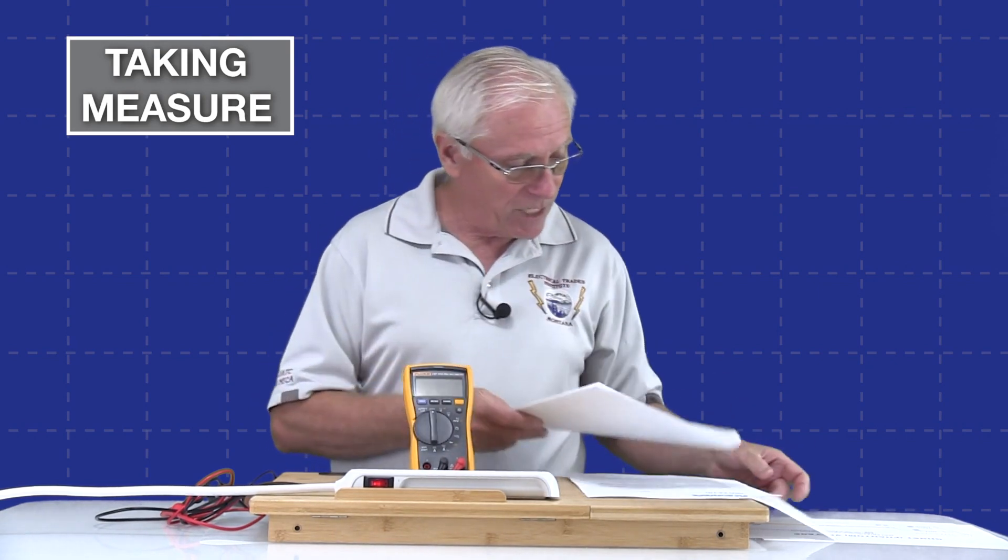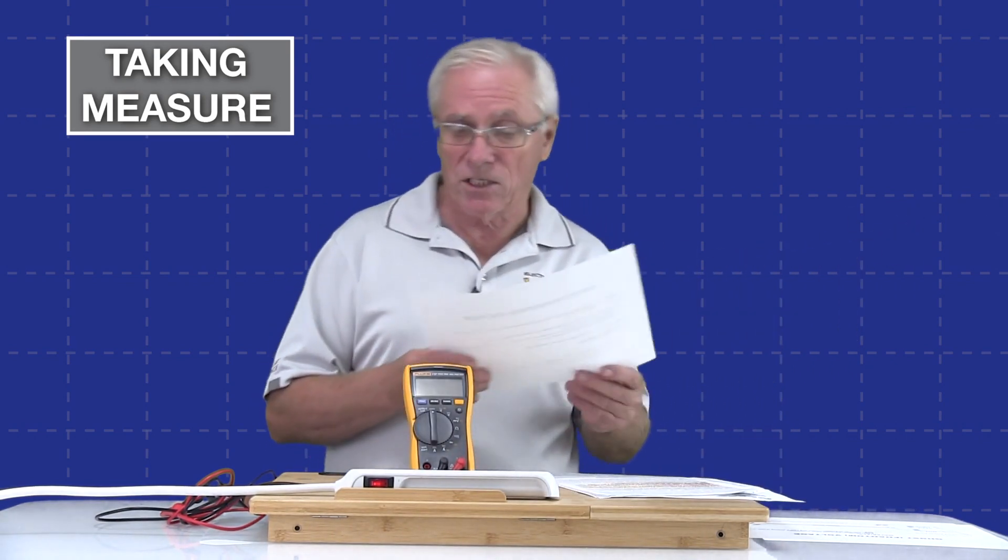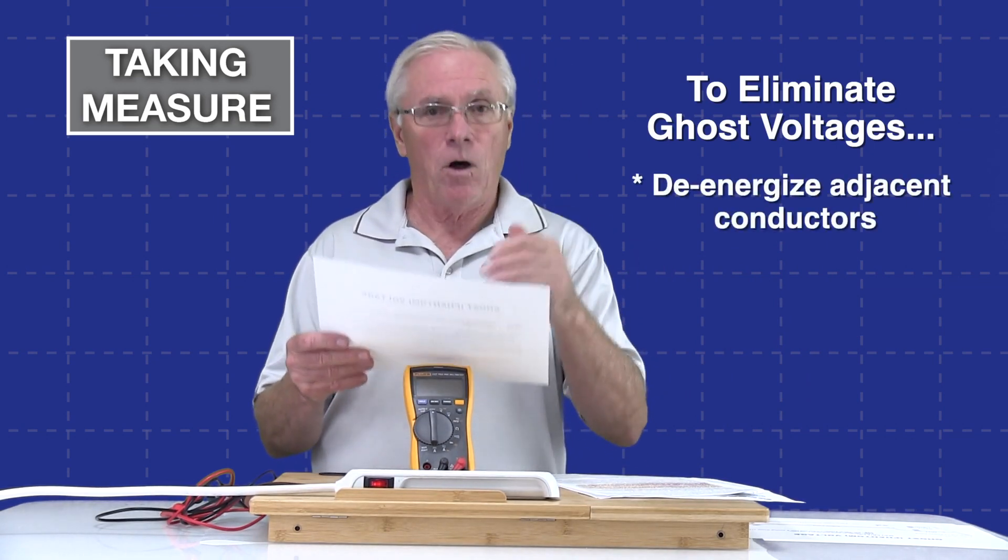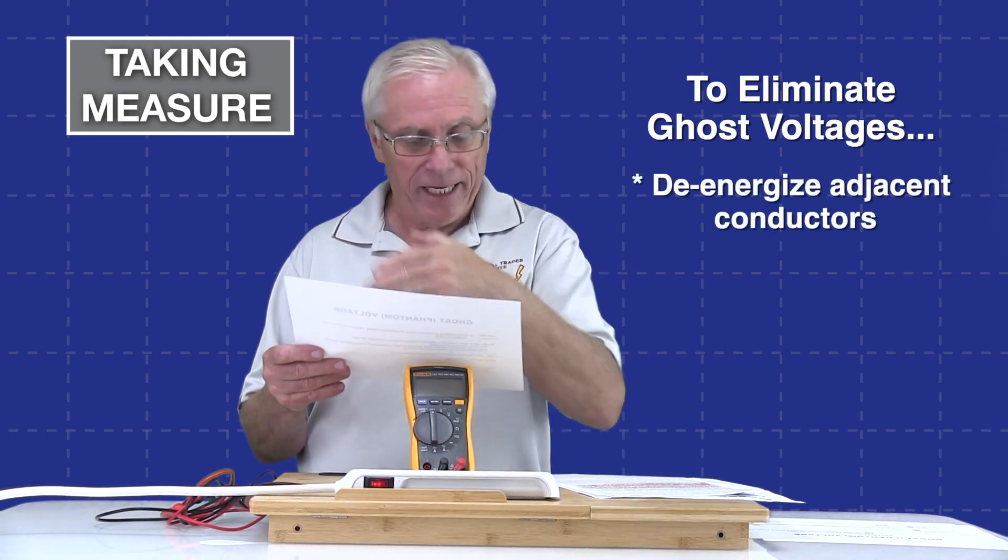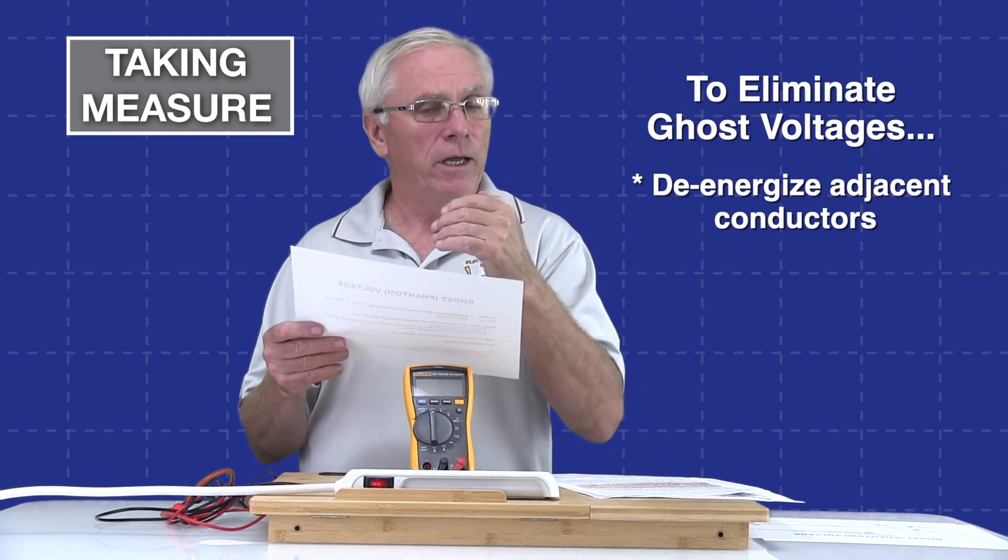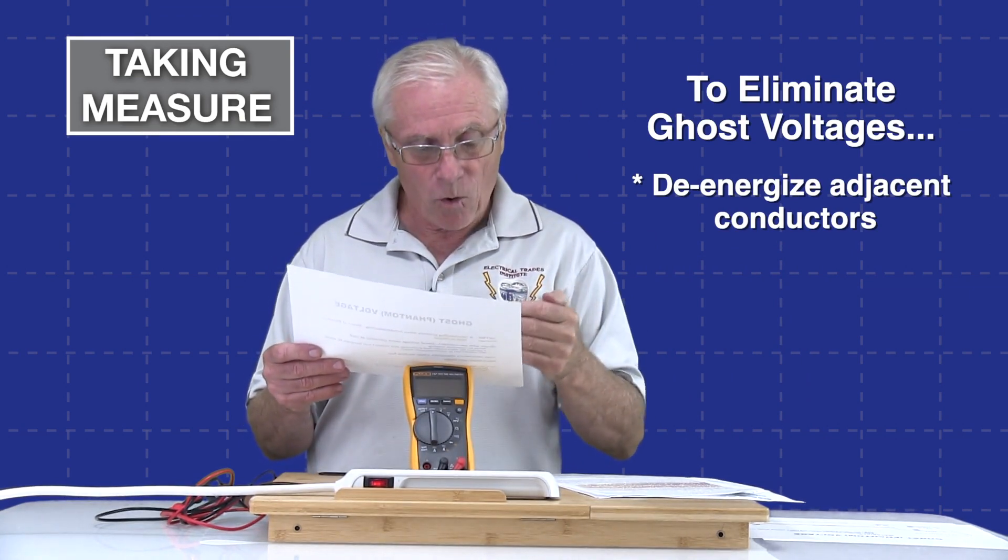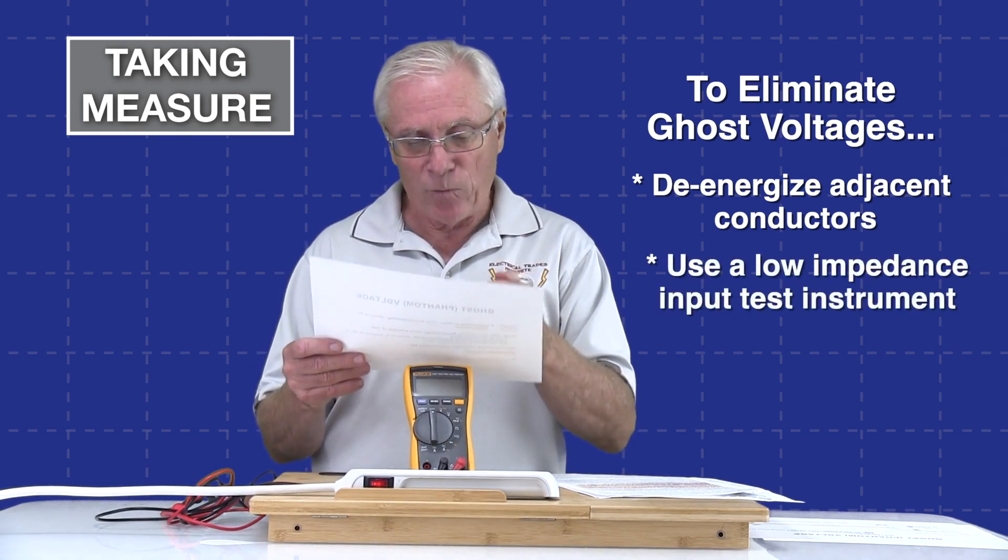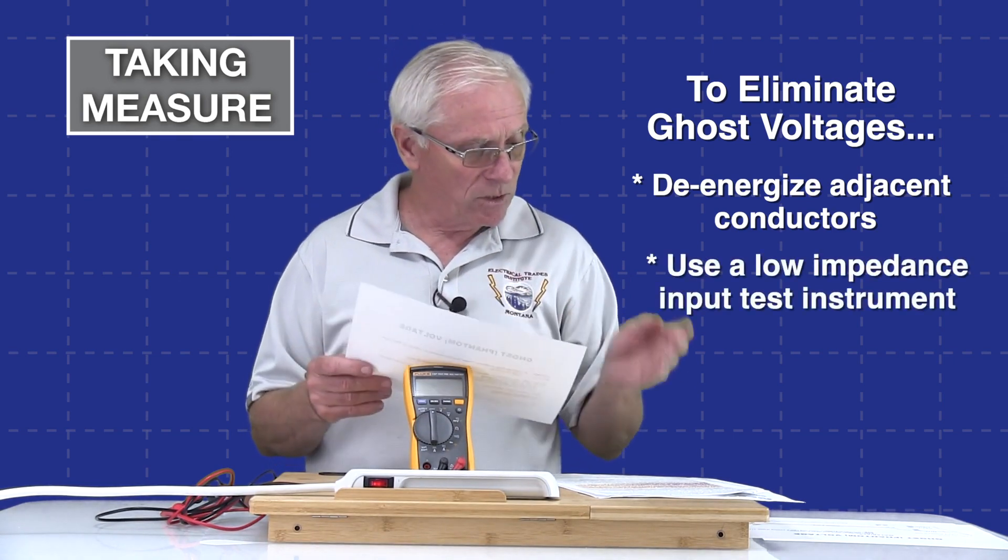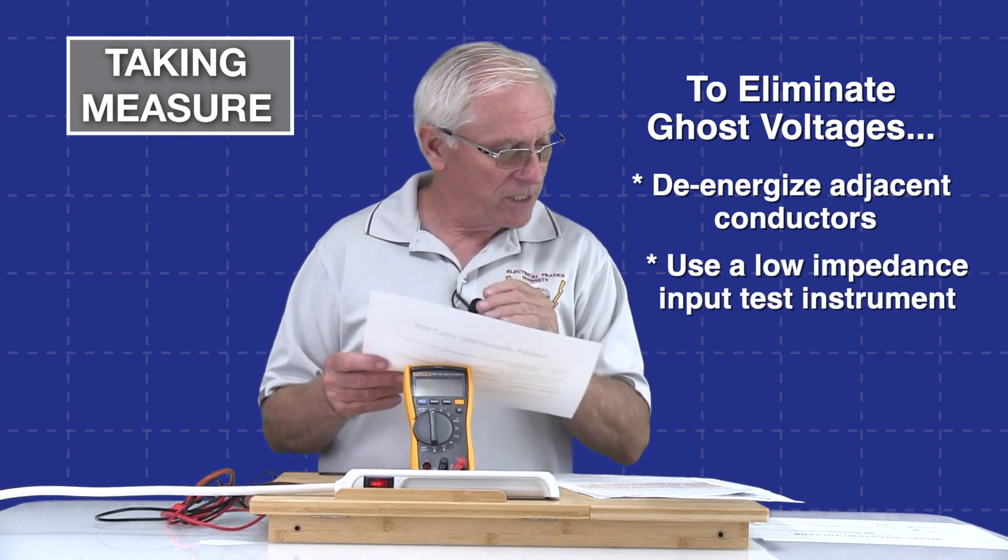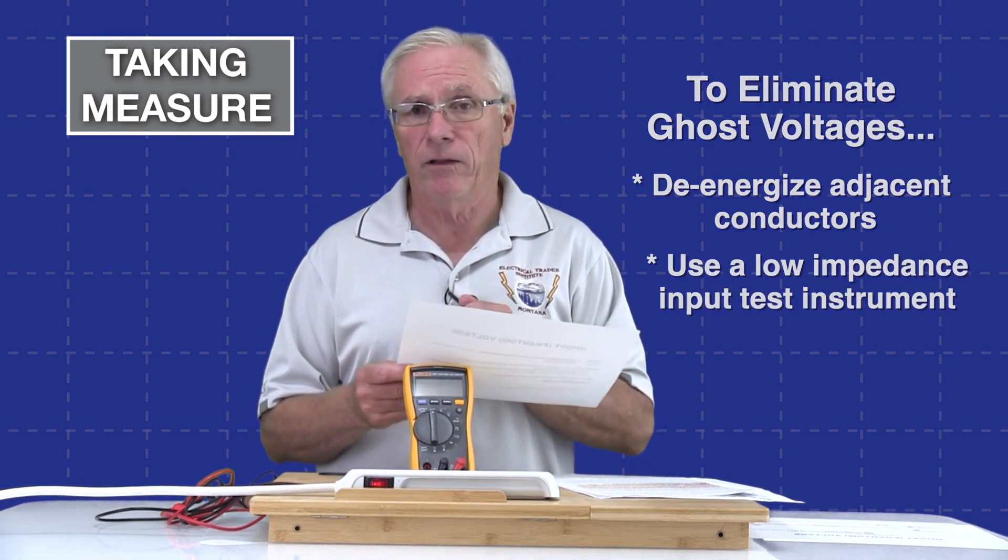Finally, I want to mention there are really two very good ways to eliminate ghost voltages. One of them is de-energize all associated conductors in a common cable or a common raceway that might be giving you that ghost voltage, or use a low impedance input instrument for testing. We'll talk about our lab here in a minute, set it up, and we will use a bunch of different test instruments and see how this works.